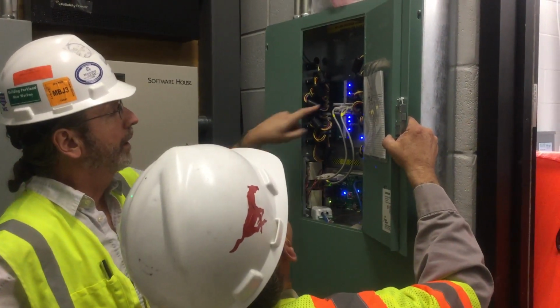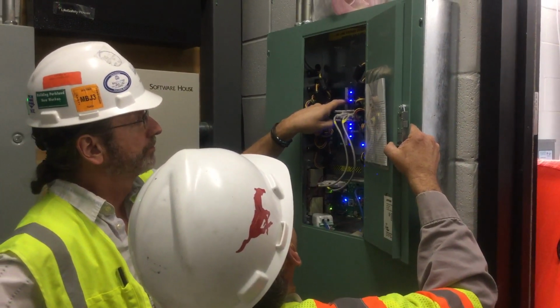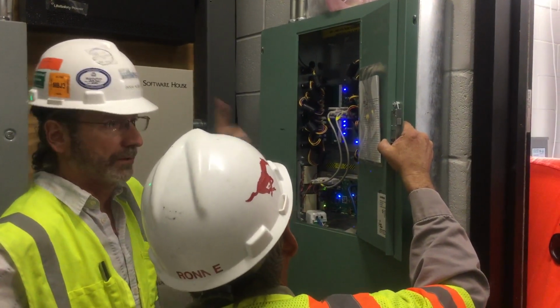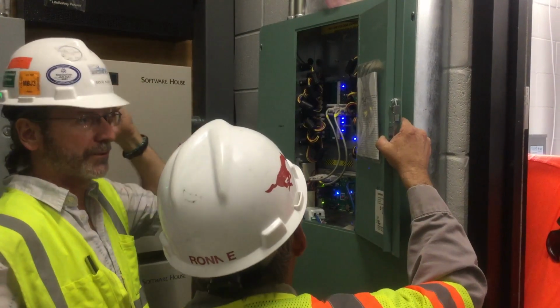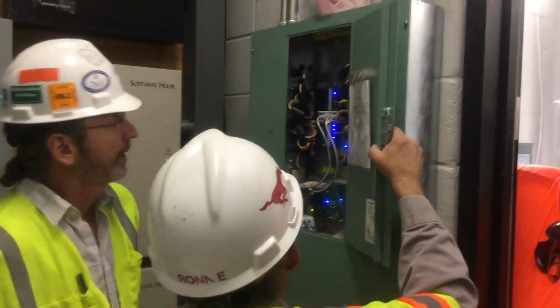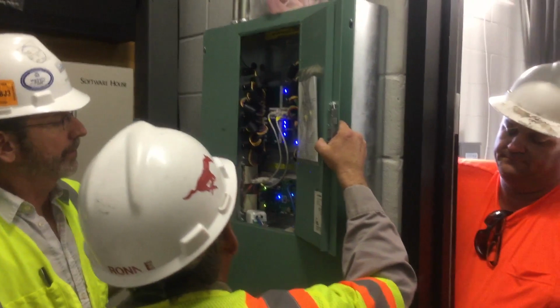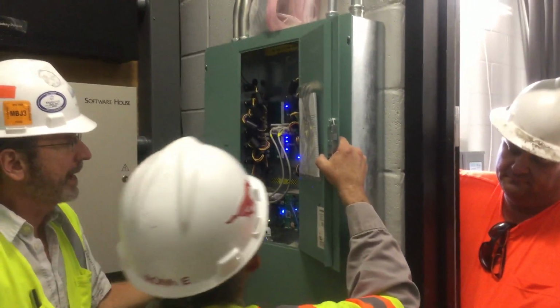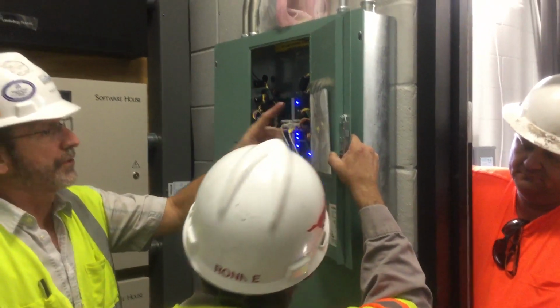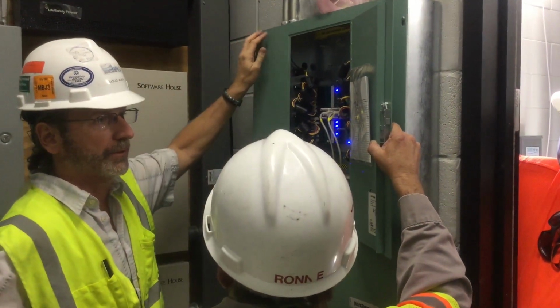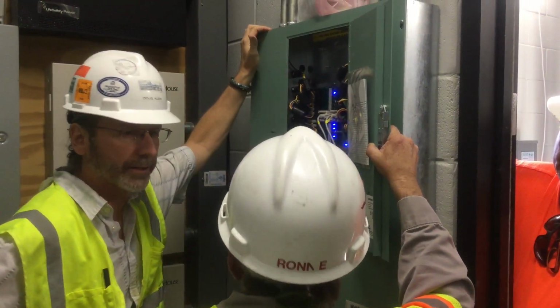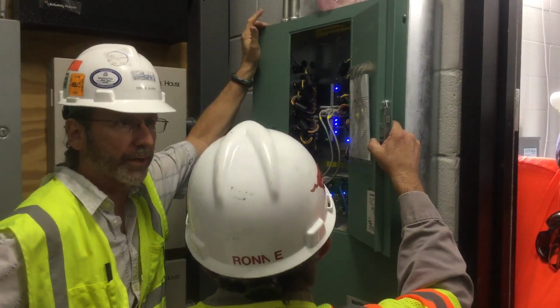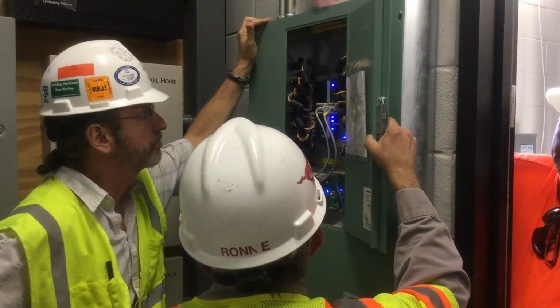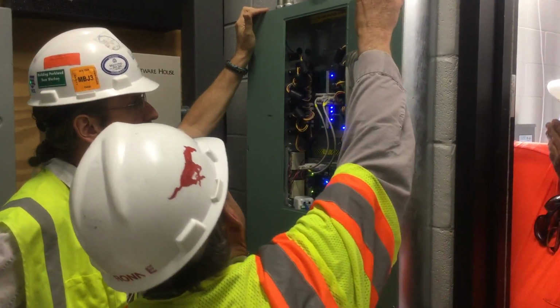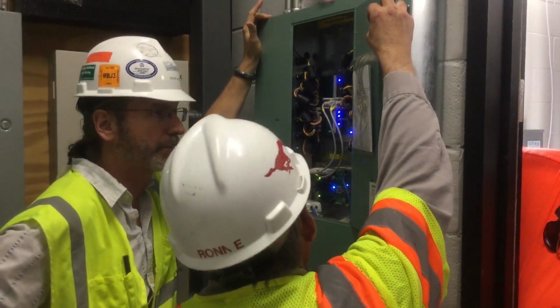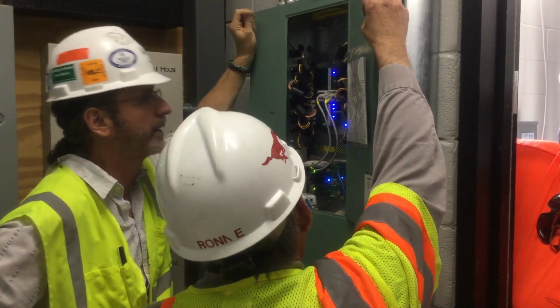This panel also has a photocell on the roof. We have two photocells up there, one for tennis, one for the relay, two separate systems. That photocell comes back into the system, and it's programmed to automatically turn on those site lighting circuits at sunset or whenever it gets dark, and turn them back off whenever it gets bright again. So right now those lights should be turning on automatically in the evening and off in the morning. The street lights are running all night.